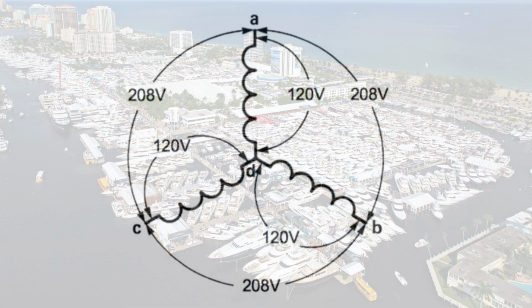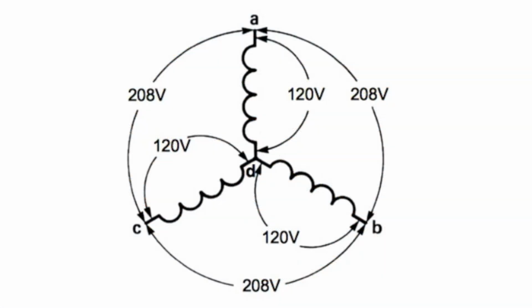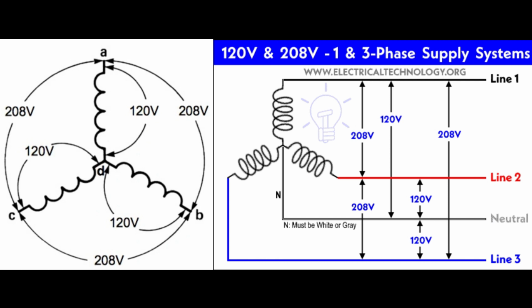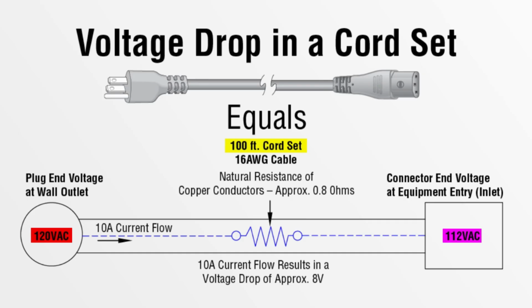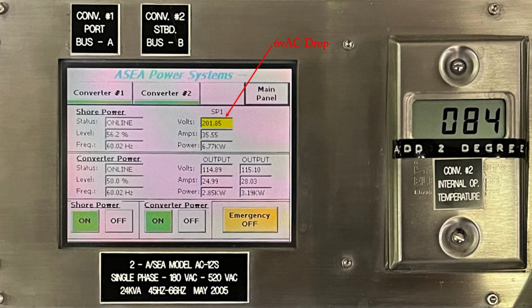In most cases these days, docks are wired with three-phase, so the 50 amp power is pulled off of two legs of this three-phase power, which gives you a starting point of 208 volts. During the summer months when the docks are crowded and everyone is either cooking, running their heating, or air conditioning, you can see voltage drops of up to 10%.